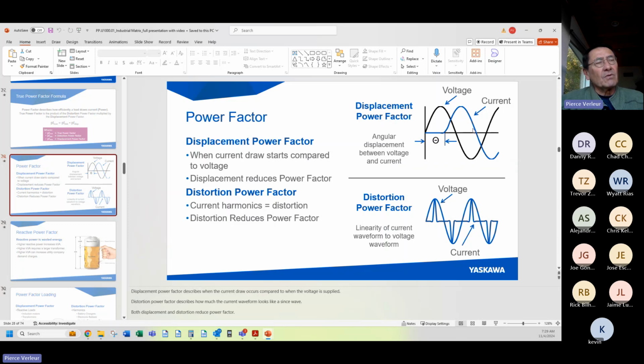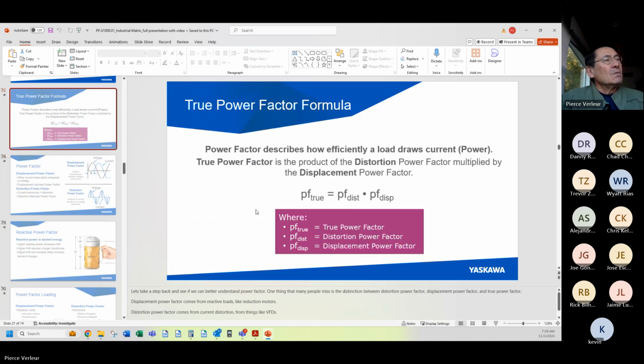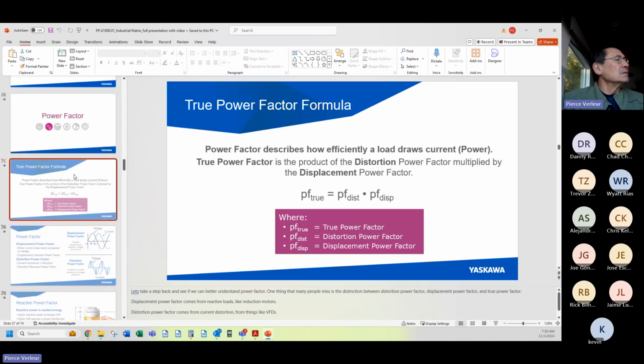This was a problem back in the old days before VFDs. Lagging current drew down the power factor, and you want your power factor to be above 90% or 0.9. Power factor is a ratio between the power that the power company gives you and the power that you actually use to move your load, whether it's water, air, a hoist, what have you. The difference being the power that's wasted.